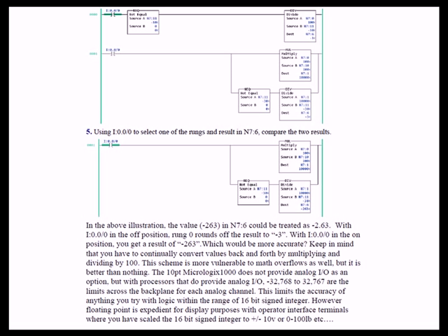Keep in mind that you have to continually convert values back and forth by multiplying and dividing by 100. Now this scheme is very vulnerable to math overflows as well, because you cut your total range down by 100. But it is better than nothing, and sometimes you want to display what appears to be a floating point on the screen of an MMI. You can simply do this by using two numeric displays adjacent to each other, and you subtract the first two positions out. You put 2 in the first numeric display and 63 in the second with a static decimal point in between the two, and it looks like it's 2.63. So this is a very difficult scheme to massage until it really works good for you, but it is better than nothing.